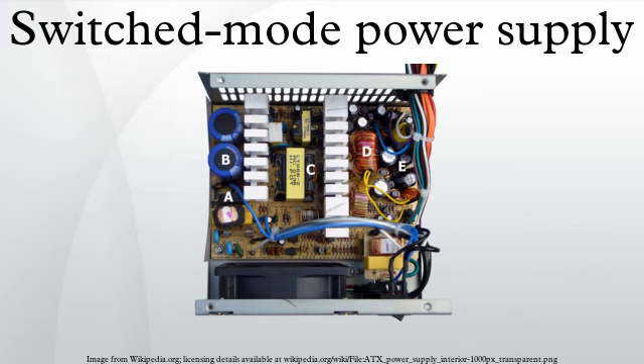Quasi-resonant zero-current zero-voltage switch. In a quasi-resonant zero-current zero-voltage switch, each switch cycle delivers a quantized packet of energy to the converter output, and switch turn-on and turn-off occurs at zero current and voltage, resulting in an essentially lossless switch. Quasi-resonant switching, also known as valley switching, reduces EMI in the power supply by two methods: by switching the bipolar switch when the voltage is at a minimum to minimize the hard switching effect that causes EMI. By switching when a valley is detected, rather than at a fixed frequency, it introduces a natural frequency jitter that spreads the RF emissions spectrum and reduces overall EMI.